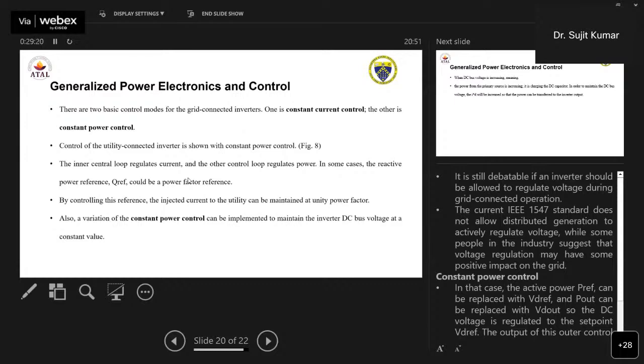A variation of constant power control can be implemented to maintain the DC bus voltage at a constant value. It is still a debate whether an inverter should be allowed to regulate the voltage during grid connected operations. It is a huge task for the inverter to regulate the voltage every time. According to the current IEEE 1547 standard, distributed generation is not allowed to actively regulate the voltage. When we go for simulation, we are not bothered that much, but according to the IEEE standards, it is not at all allowed.